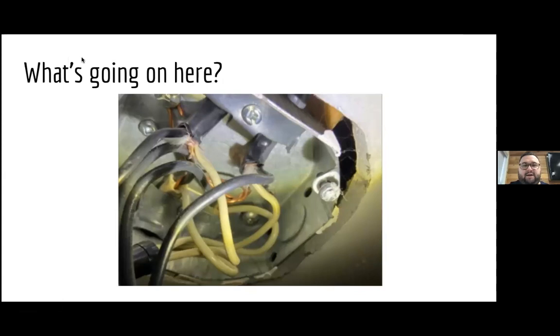How about this photo here? This is probably a tough one. I think that the colors don't match. It looks like spaghetti. Yeah. So this is actually tricky. And again, you know, it's one of those things that unless you are a certified electrician, you're probably not going to catch it. So this is a this is the bar junction box for a light fixture that's installed into a ceiling. And it's actually ungrounded. So there's no grounding wire in there, which means that, you know, that device is just it's not being grounded. I always say grounding is the most important part of your home. It's taking any of that excess electricity that comes into the system and putting it as fast as possible down to the earth so that you don't get shocked or your devices don't get damaged. So, again, it's the same thing. This is the kind of situation where people can potentially get hurt or devices can potentially get ruined if you don't know what you're looking at or working with.